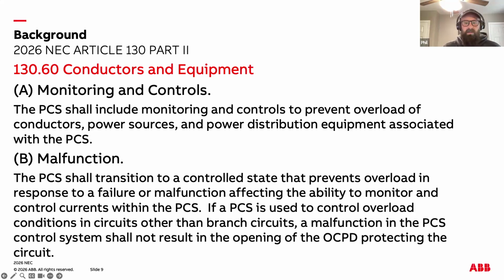If the PCS loses communication, loses power, or experiences a fault, it must default to a state that does not allow an overload to occur. Overcurrent protective devices, breakers, remain the final layer of protection, but PCS must not create unsafe conditions.